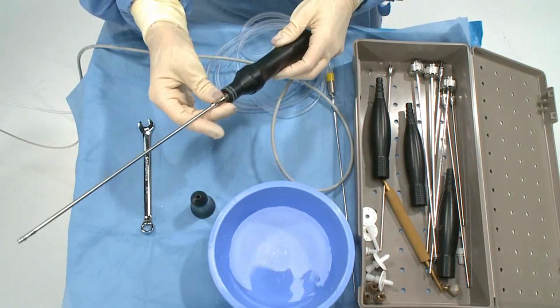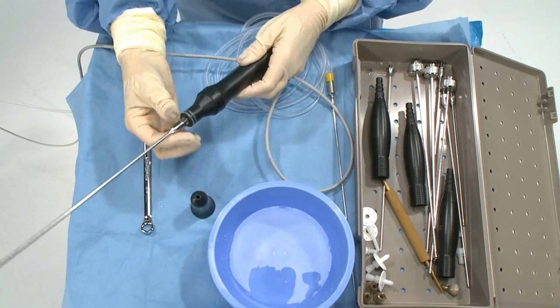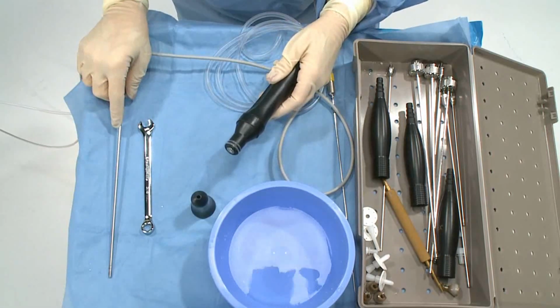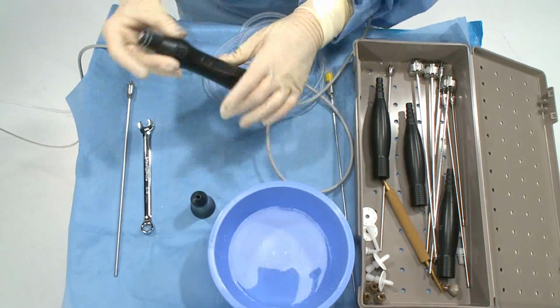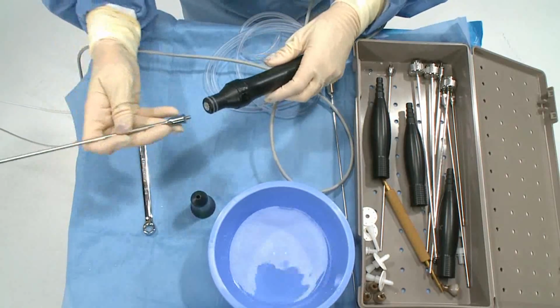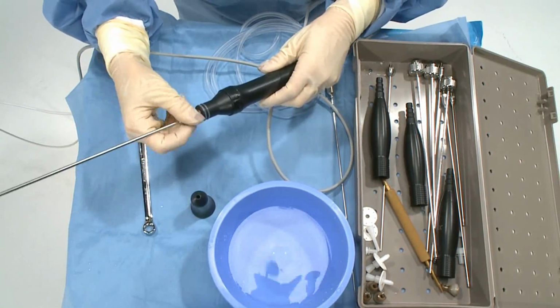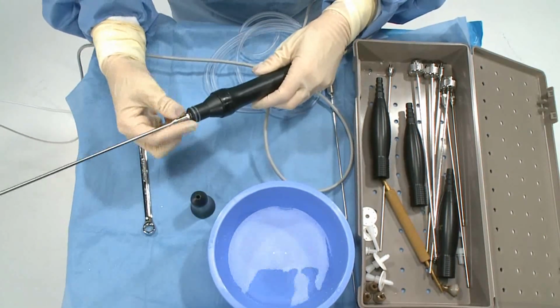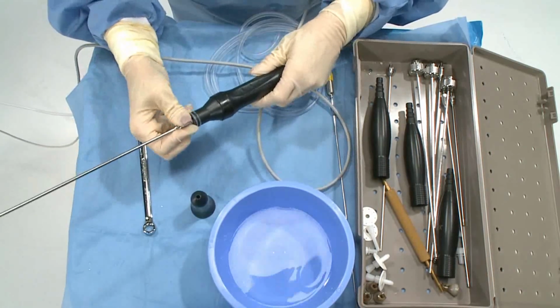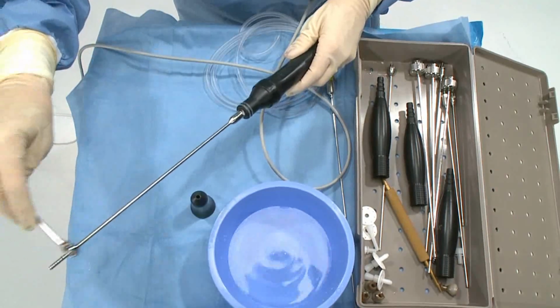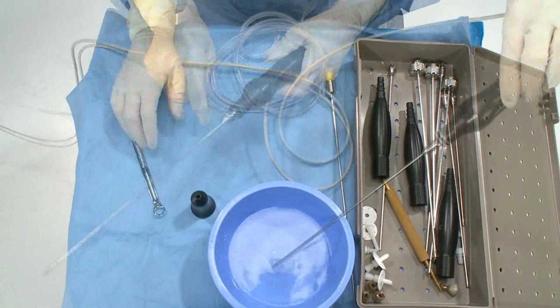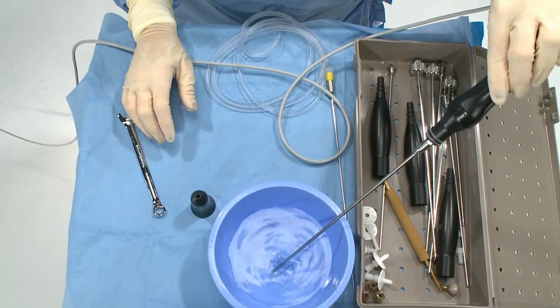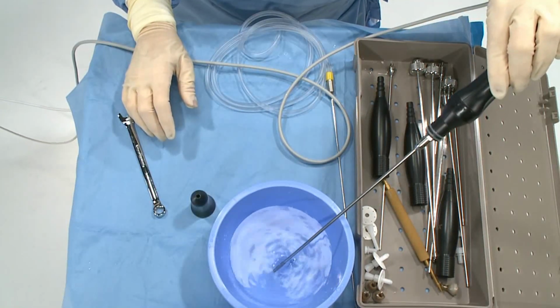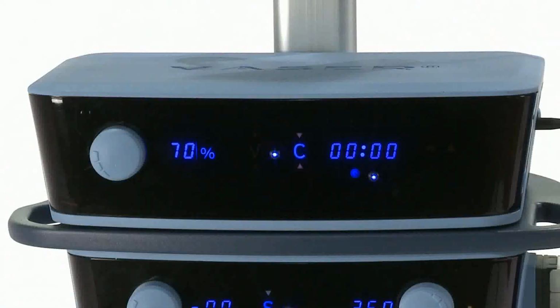Additionally, check the probe alignment. If the probe is not tightened or aligned correctly, you will usually hear a chattering sound when the ultrasound is activated. If this occurs, disassemble the probe, realign, tighten, and retest. If you continue to experience issues, contact technical support.